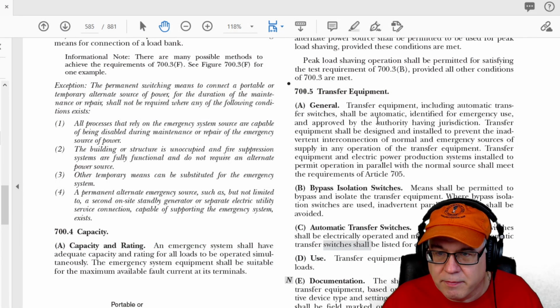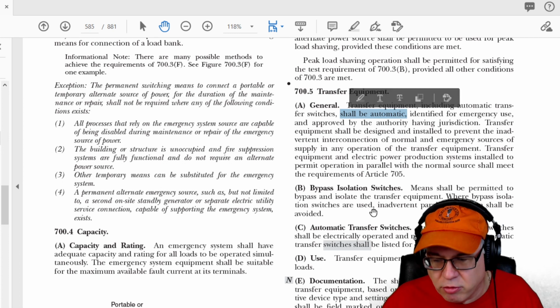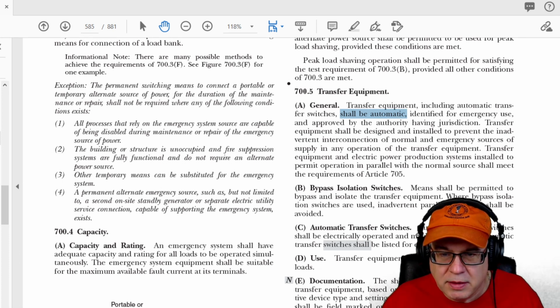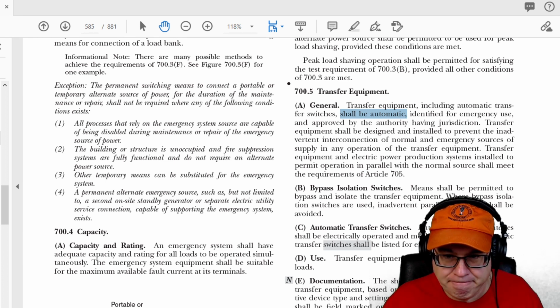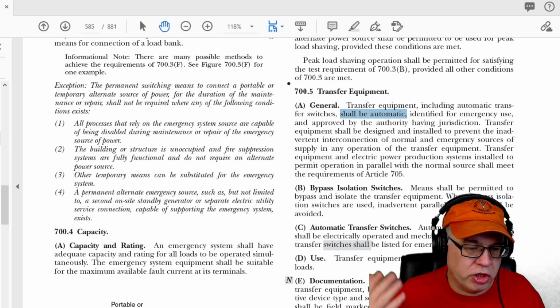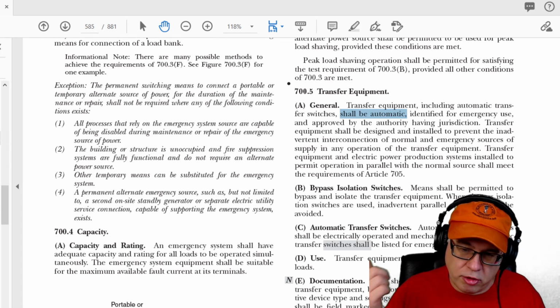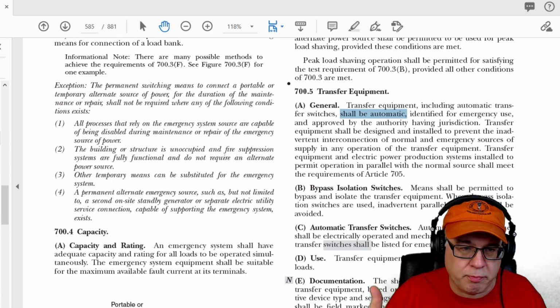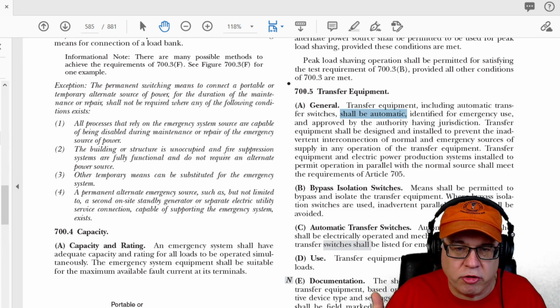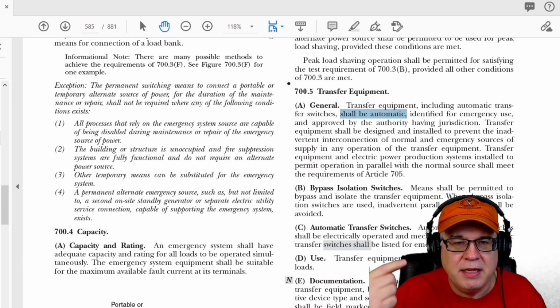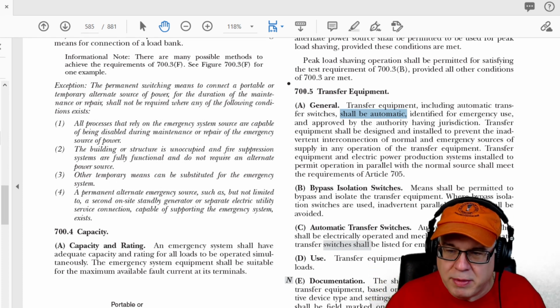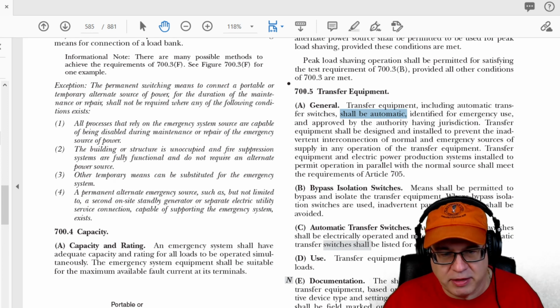Let's go back to our NEC right here. Automatic, it says it shall be automatic. Can't be manual, the only one that can be manual is the optional standby. But you could have used legally required, you could have used automatic, all of those. You could have gone to the back of the book and used legally required, or gone back and looked under emergency and you would have seen transfer equipment. So there's so many good ways to get the answer for that one.